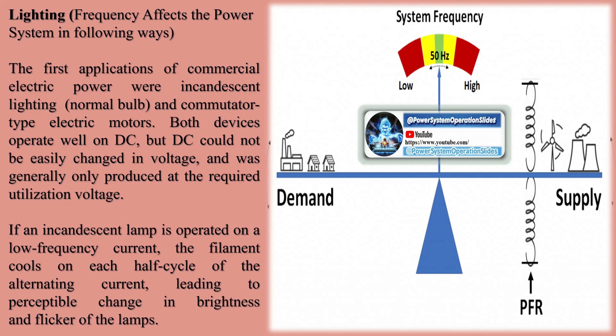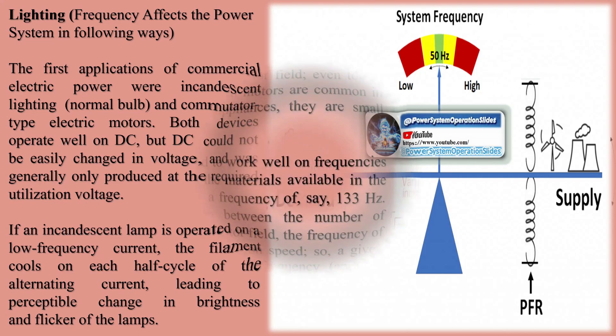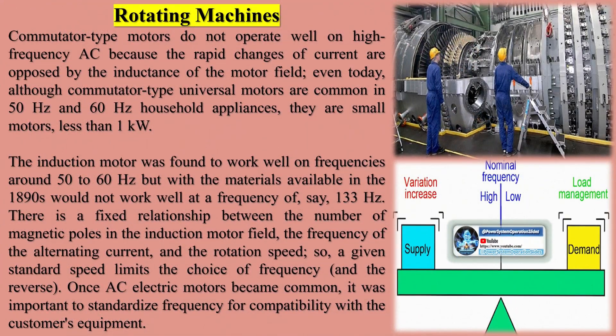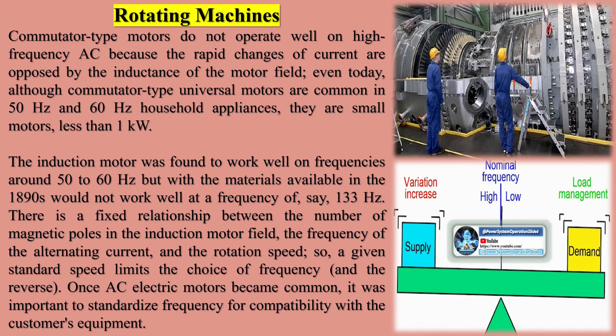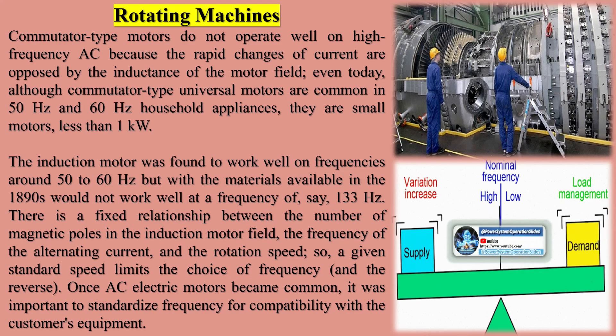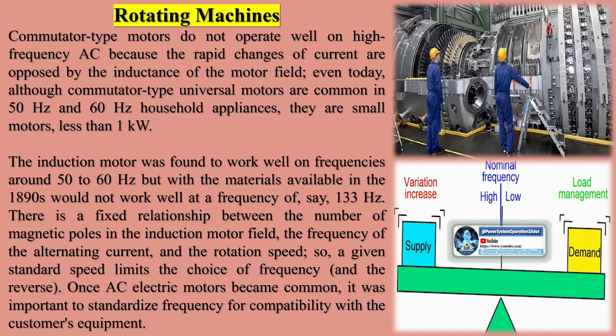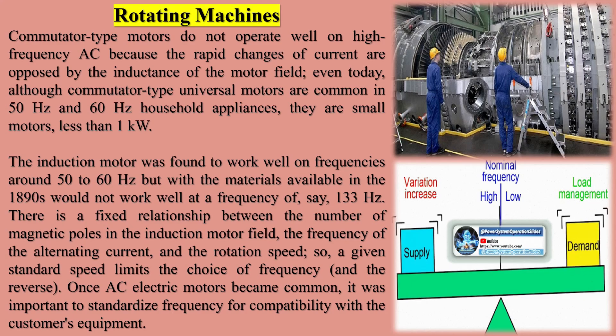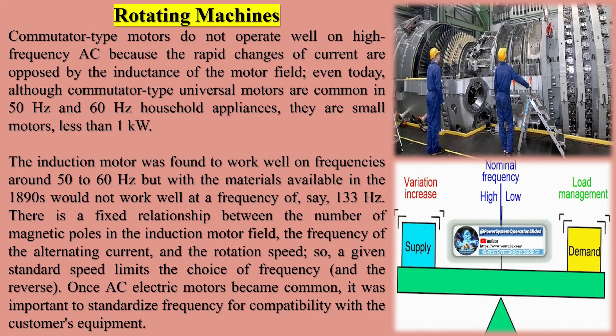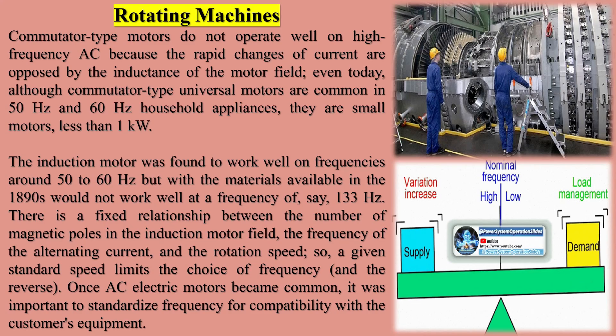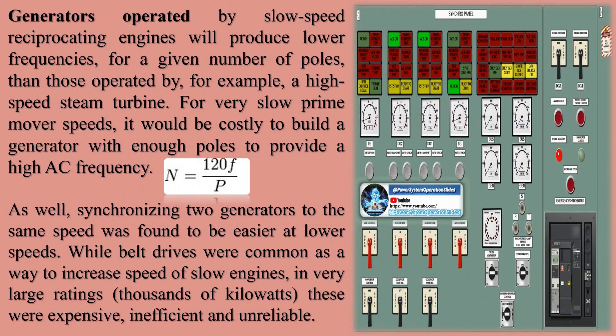There is a fixed relationship between the number of magnetic poles in the induction motor field, the frequency of the alternating current, and the rotation speed, so a given standard speed limits the choice of frequency and the reverse. Once AC electric motors became common, it was important to standardize frequency for compatibility with the customer's equipment. Generators operated by slow-speed reciprocating engines will produce lower frequencies for a given number of poles than those operated by, for example, a high-speed steam turbine. For very slow prime mover speeds, it would be costly to build a generator with enough poles to provide a high AC frequency. Also, synchronizing two generators to the same speed was found to be easier at lower speeds.